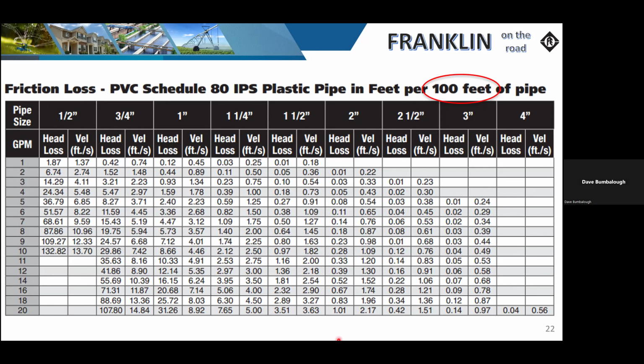We don't want the water flowing in the pipe past 5 feet per second. You'll see a lot of these charts reflect that velocity measured in feet per second. You want to stay under 5. If you get past that point, especially if it picks up particulates in the well, you can start sandblasting the material, and eventually you'll blow a hole in something. And if it's making a 90 or a T connection, you can get what we call water hammer in the system. So you want to be very careful on that velocity. But as we look at this chart, it's basically sizing it in 100-foot lengths.